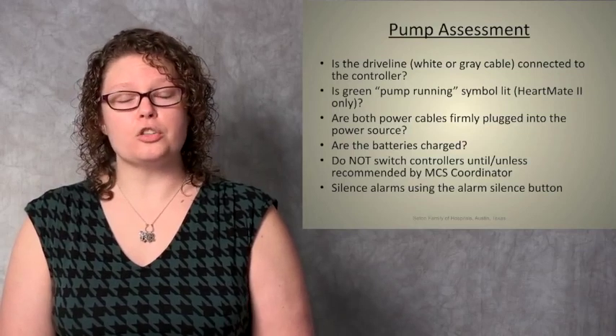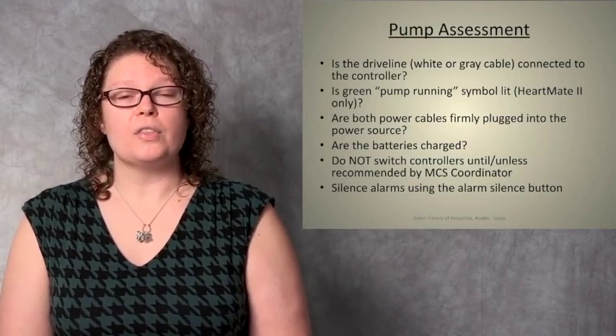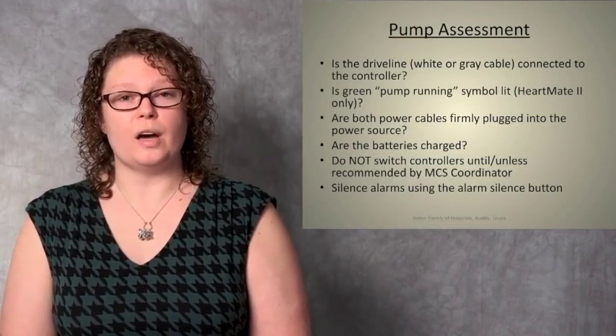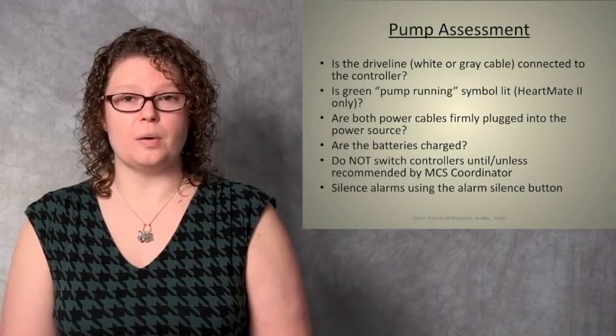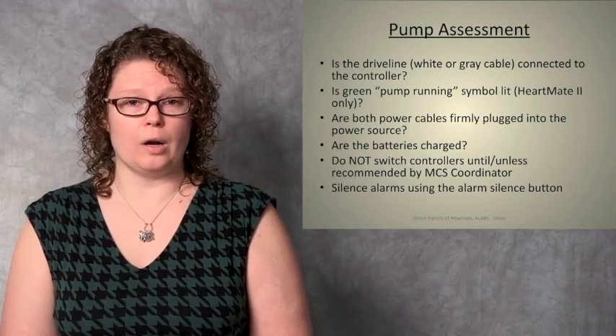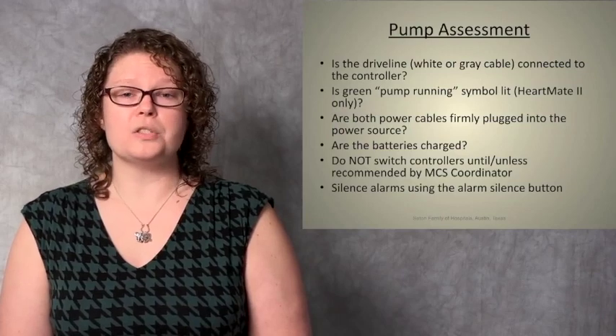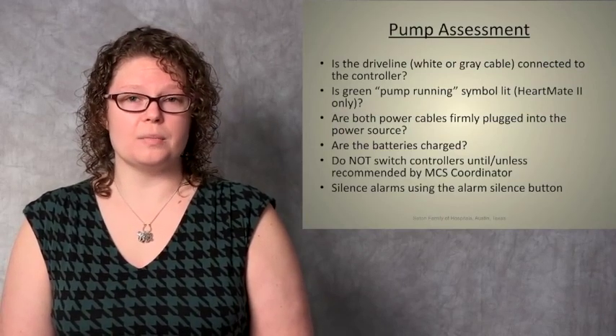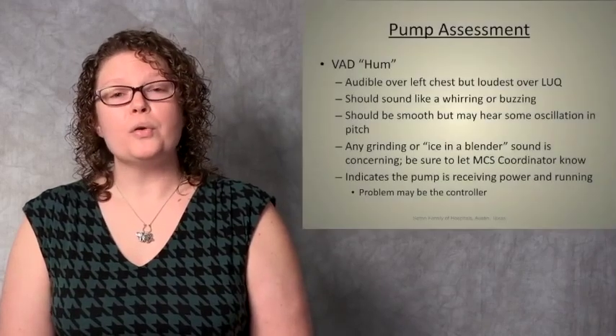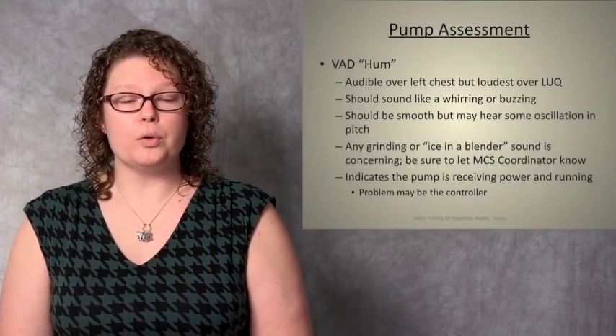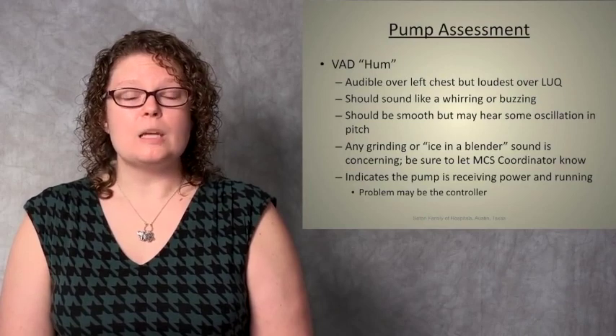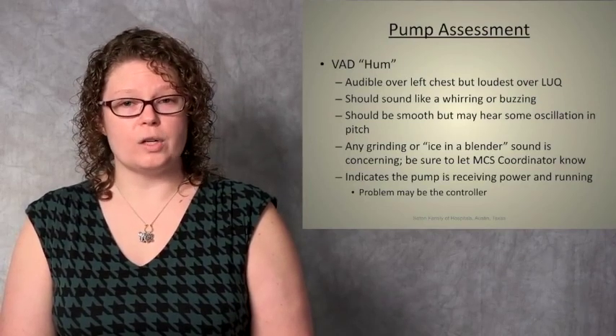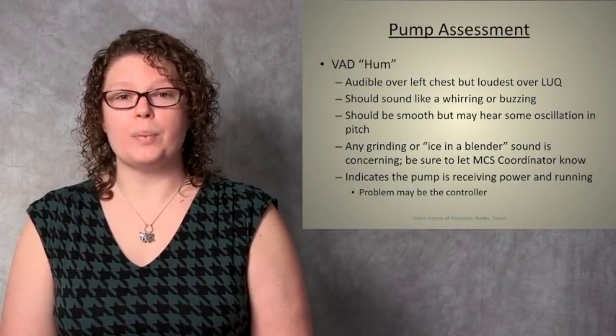In terms of switching controllers, I will demonstrate that today, but that is something that we don't want you to do without us on the phone so that we can assist you, as there's a high potential for things to go wrong in that situation. And always use your silence button to silence the alarms. You can use your stethoscope to listen for the VAD hum. Both of these pumps will be audible using a stethoscope over the chest, typically loudest over the left upper quadrant, and it should sound like a whirring or a buzzing noise.